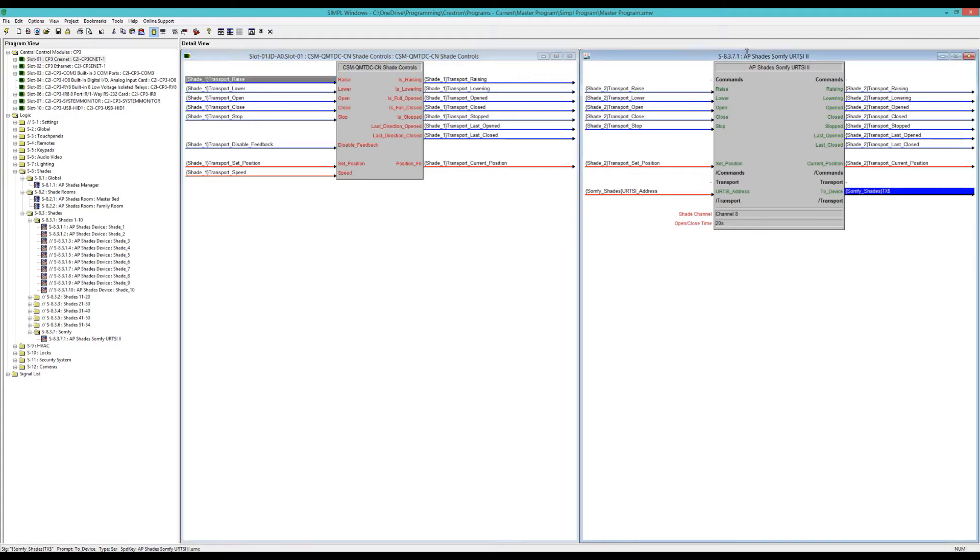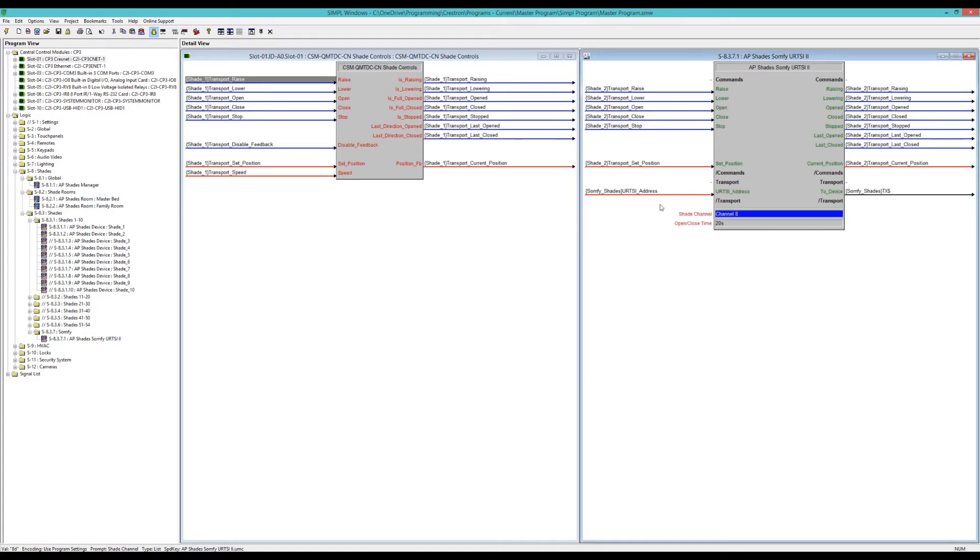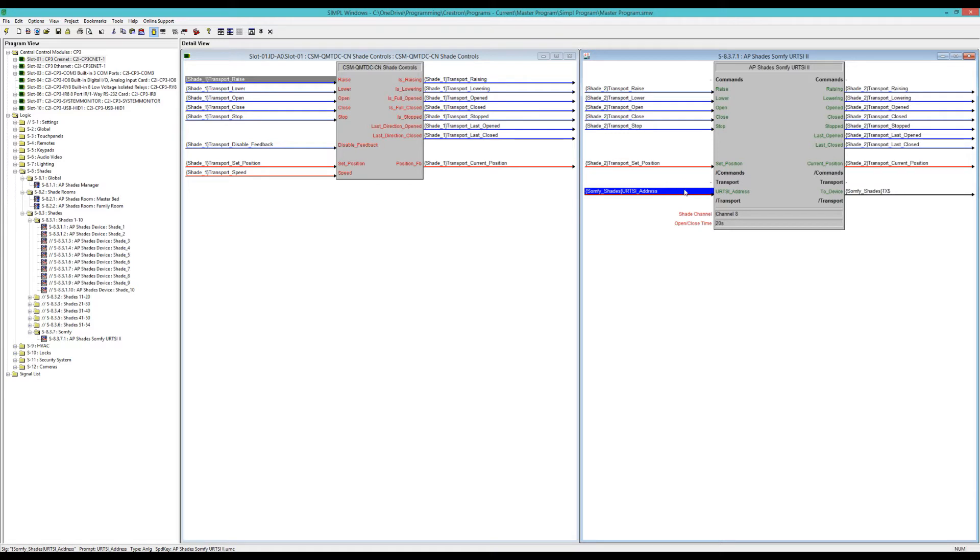In the module itself, the only other thing you have to do is set the channel in which you program the shade to on the URT-SI, and the URT-SI address, which I just made an analog string so you can feed it to all your modules instead of putting it in manually in each one. So I figured that was a little easier. And then obviously the TX signal to the RS-232 device.